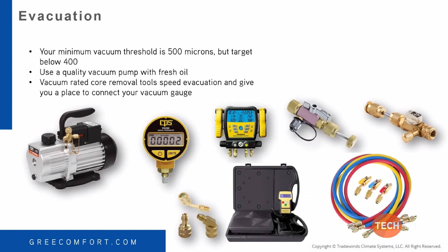So how often should you change your oil? Well, it depends on what you're doing. If your vacuum pump is strictly being used for new installation, your oil will last a while. You're probably going to be a while before you have to change your oil. But if we're servicing the unit, we've had a leak in it, and now we have to evacuate the entire system, including the condenser, that's a whole other conversation about how we go about doing that evacuation. But you can do a bunch of installs and not have to change the oil when you're just pulling down refrigerant lines on a coil.